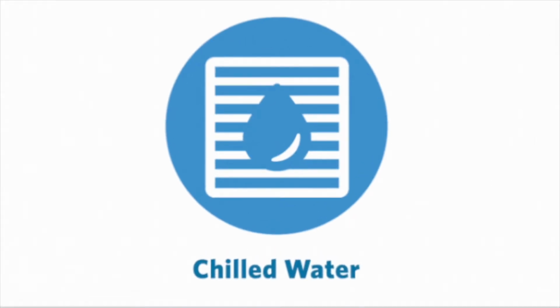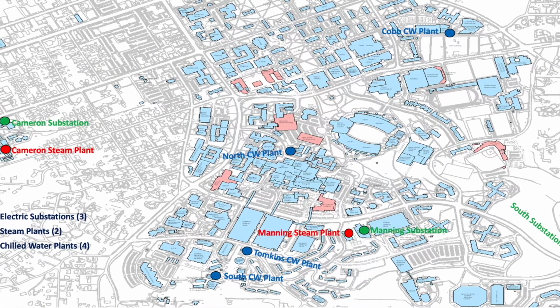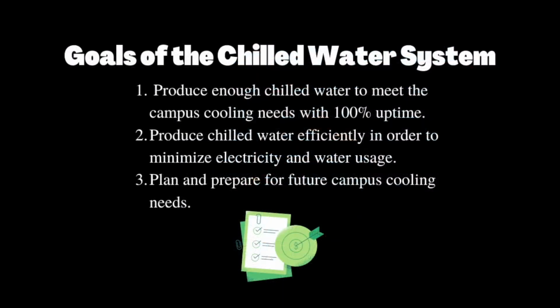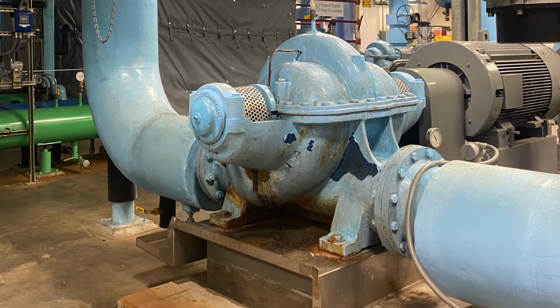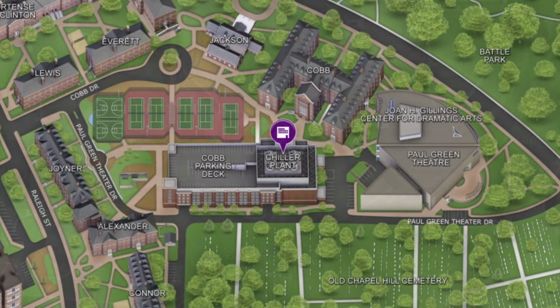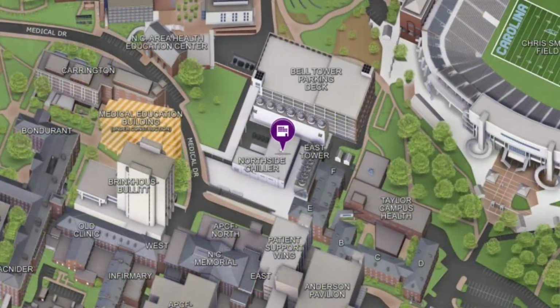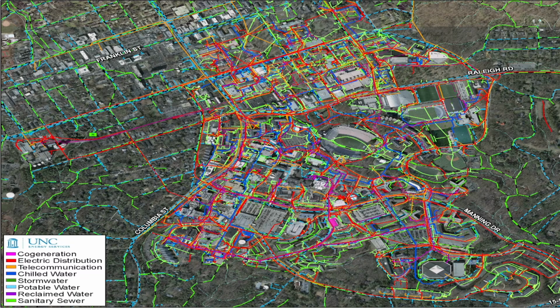for the cooling of approximately 155 buildings across campus. The goals of the chilled water system are to produce enough chilled water to meet the campus cooling needs with 100% uptime, produce chilled water efficiently in order to minimize electricity and water usage, and plan and prepare for future campus cooling needs. The chilled water system is composed of 4 interconnected chilled water plants spread out around campus. The plants are connected via 27.5 miles of underground piping, and green and red caps can be easily spotted throughout campus that indicate where the piping resides.